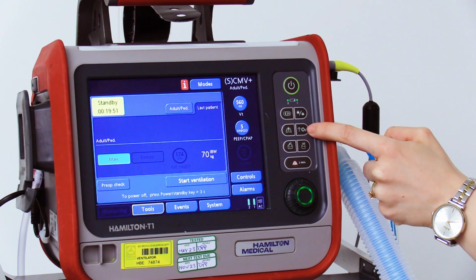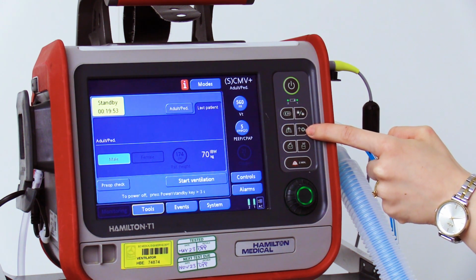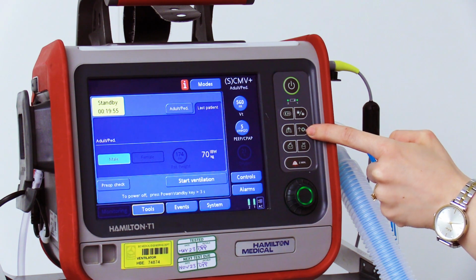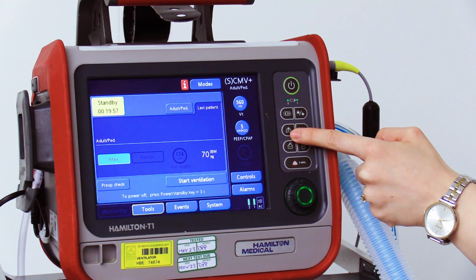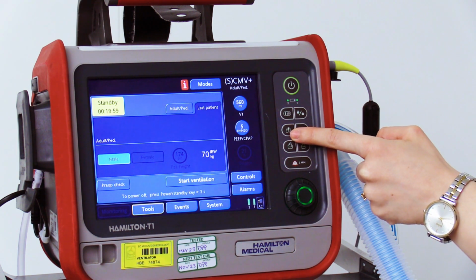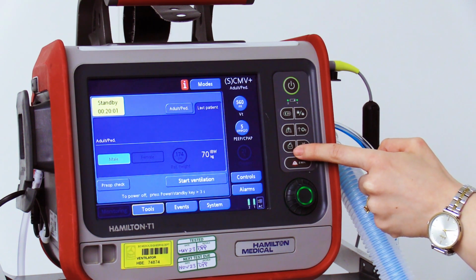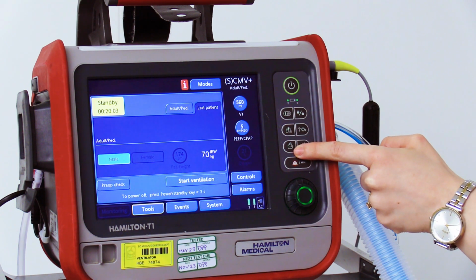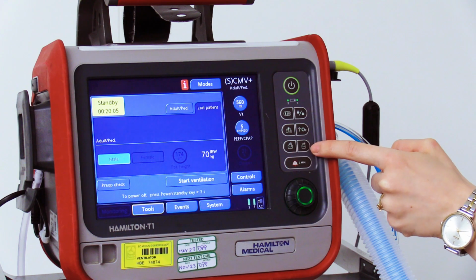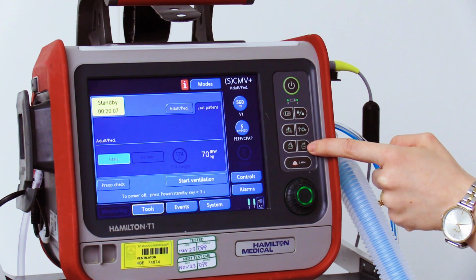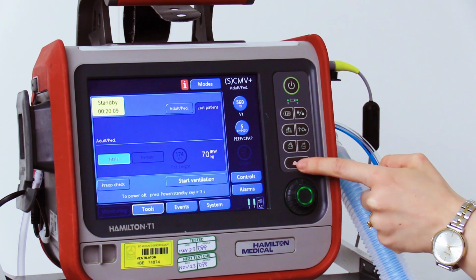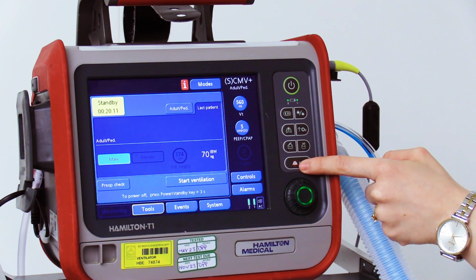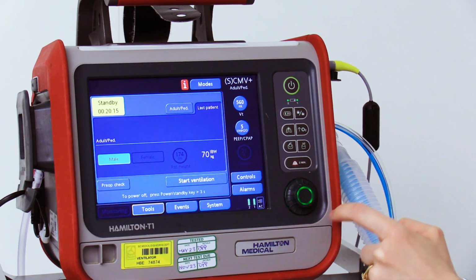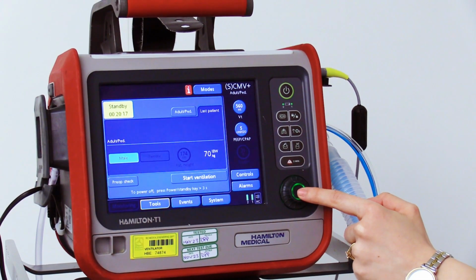This is the oxygen enrichment key that provides 100% oxygen. Next is the manual breath key, and it's for inspiratory hold as well. Below that is the print screen for downloading screenshots into the USB. The nebulizer button here provides 8 liters per minute of oxygen for 30 minutes. Then the alarm silence key. Below that, you can see the rotate and press knob.